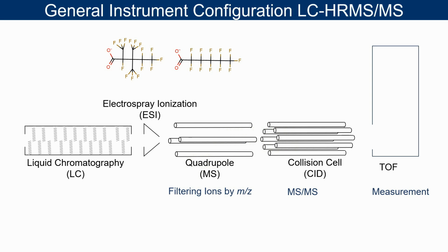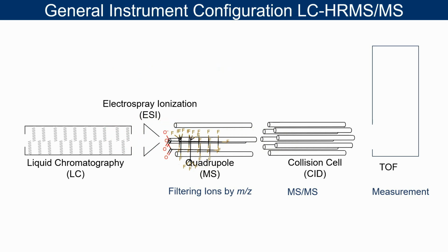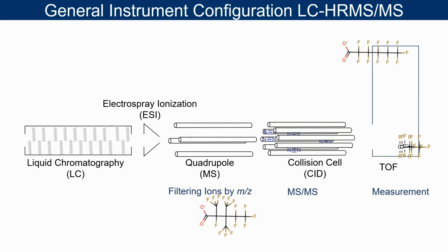They might coelute, which means come out at the same time. And so for that purpose, when we use the quadrupole, we isolate a molecule before we fragment that molecule into pieces, which we measure in the QTOF. So again, with the QTOF, it would be very similar. You can get your accurate mass scans, or you can fragment to get your fragmentation scans. Also with the QTOF, because of the speed, we can also include ion mobility, which we won't discuss here.